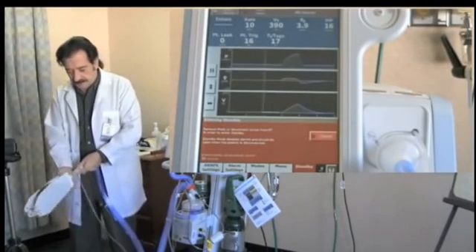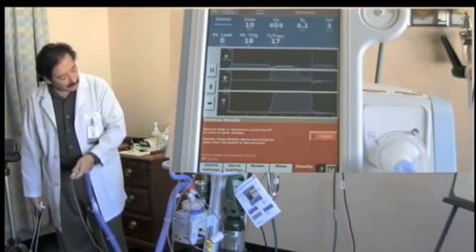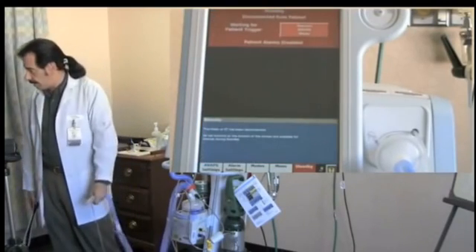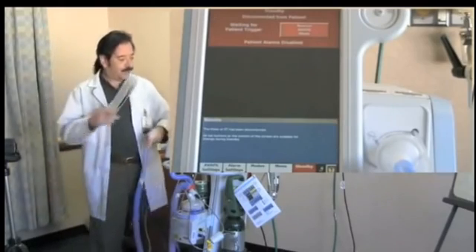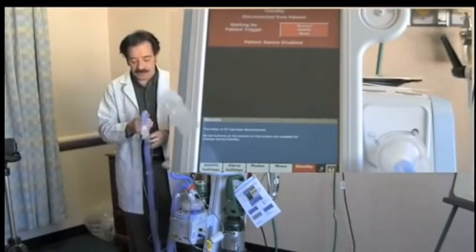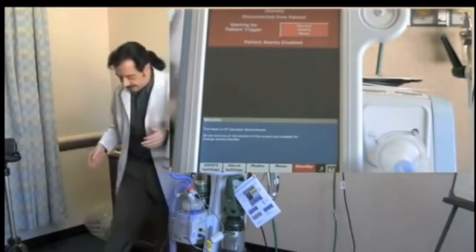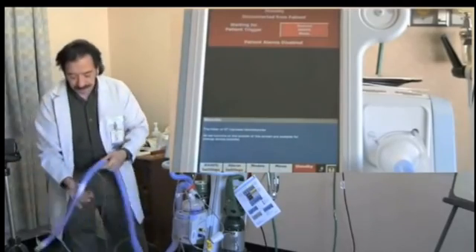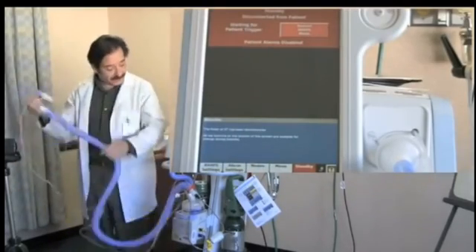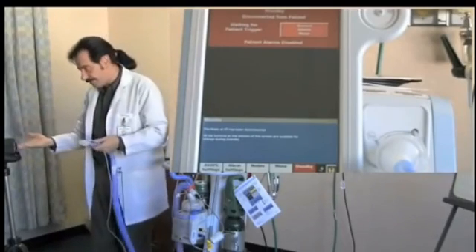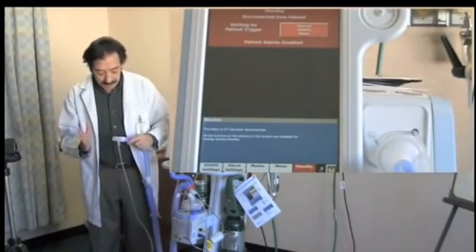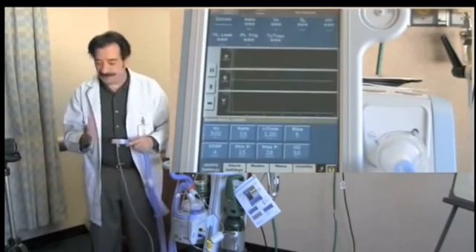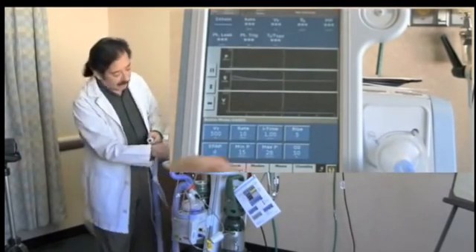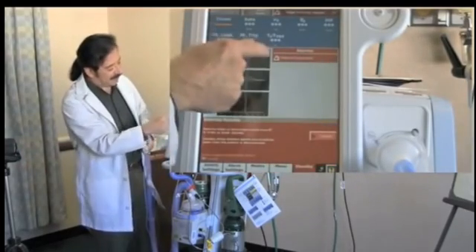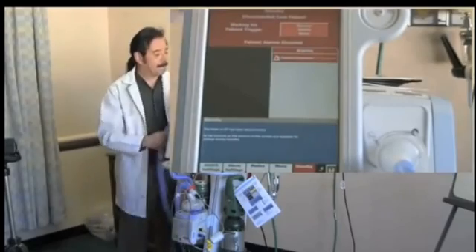So I disconnect the patient. The flow comes out as normal. Then it ramps down and it goes into standby all by itself. Now, one of the problems with the old Vision was if you jostled the circuit, or you dropped it, or you kicked it, or whatever, then it would fall out of standby and start alarming, disconnect alarm. So this is obviously much more robust. Okay, it's not going to fall out of standby. It's not perfect though. You can fool it. If I tap on the tubing there, see, it fooled it and fell out of standby. So it's not perfect, but it's certainly better than it used to be.